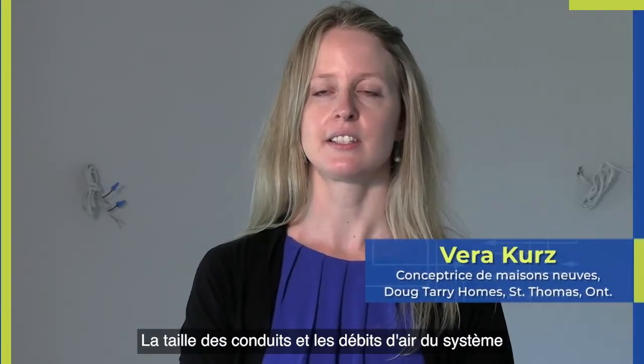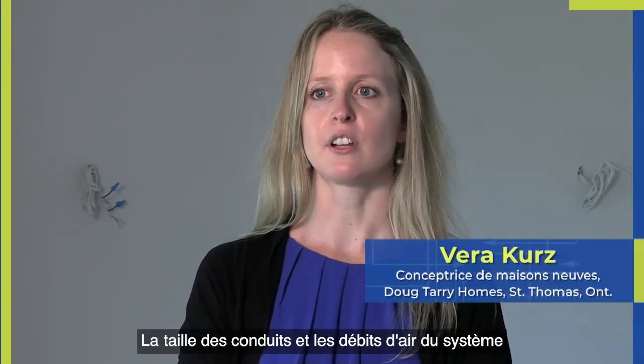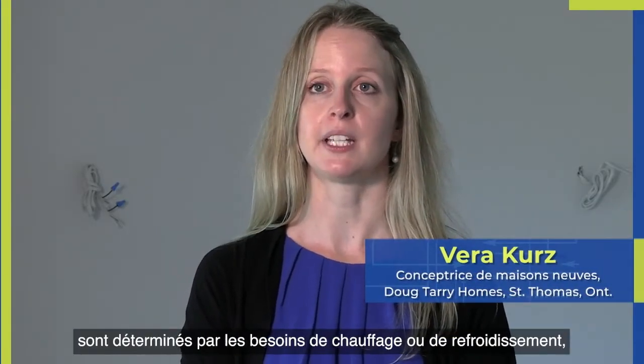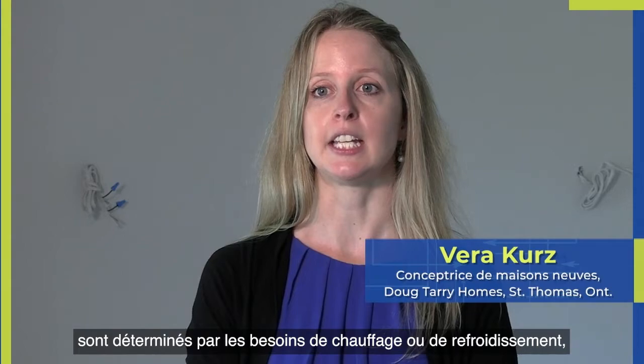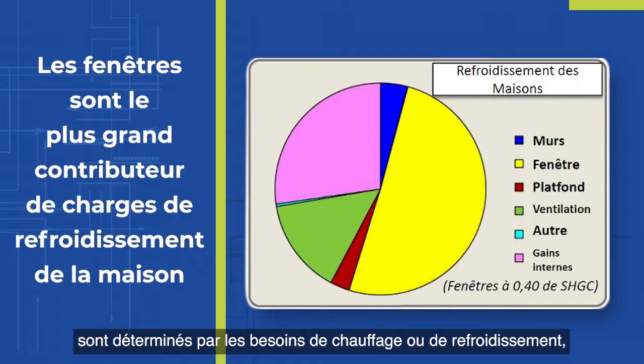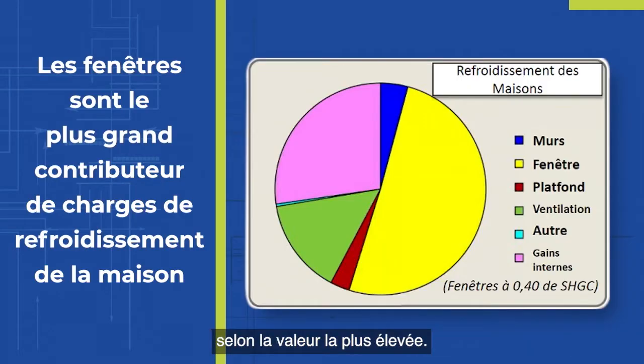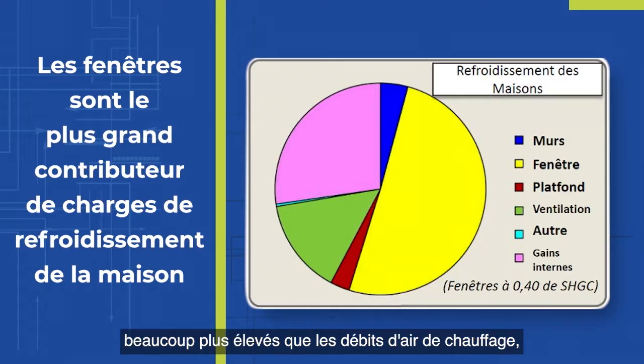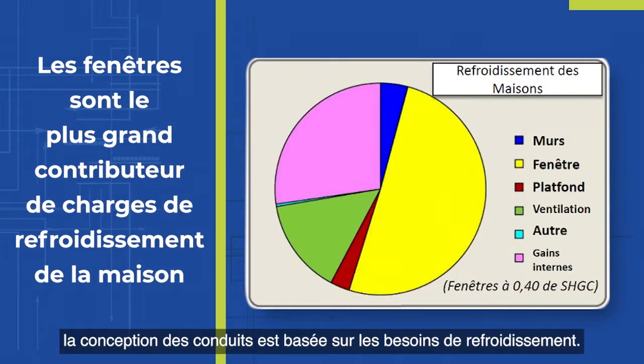Duct sizes and system air flows are determined by either the heating or cooling requirements, whichever is larger. So when cooling air flows are a lot higher than the heating air flows, the duct design will be based on the cooling requirements.